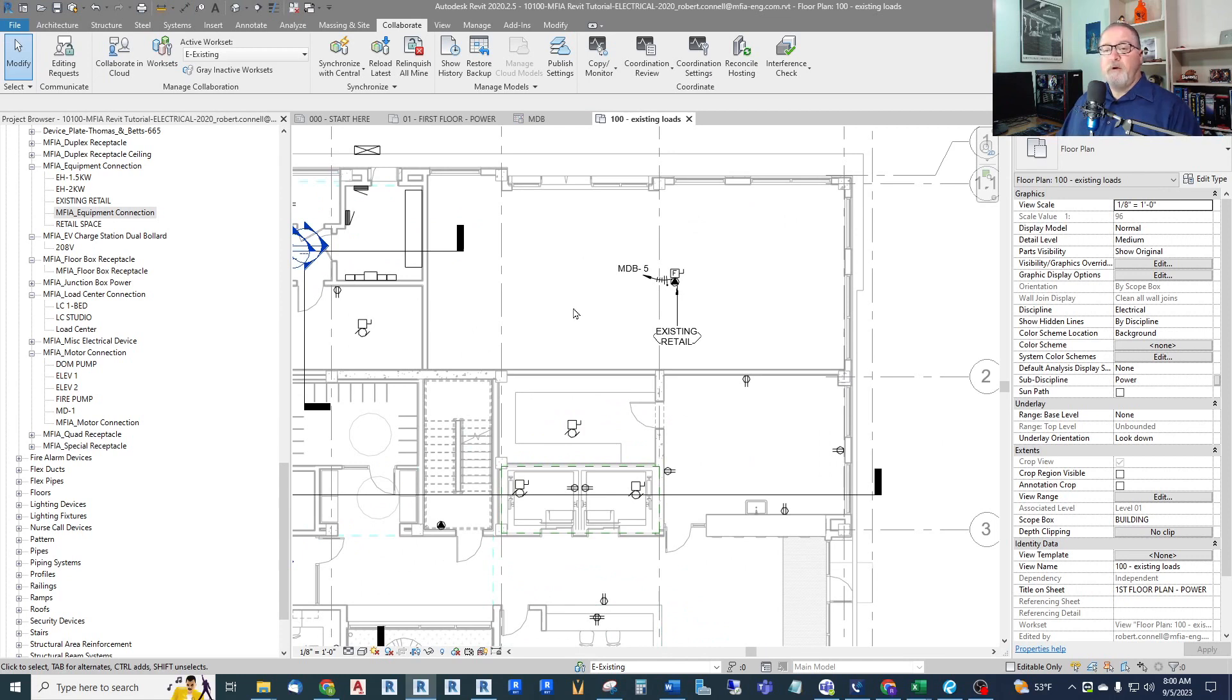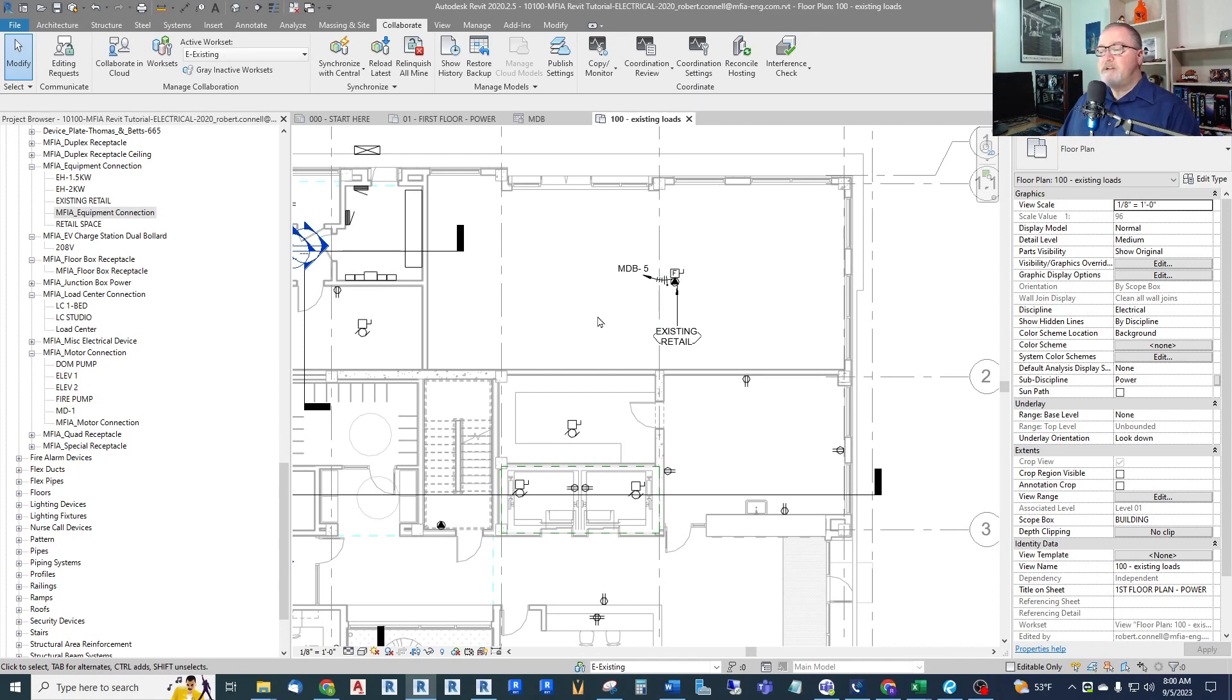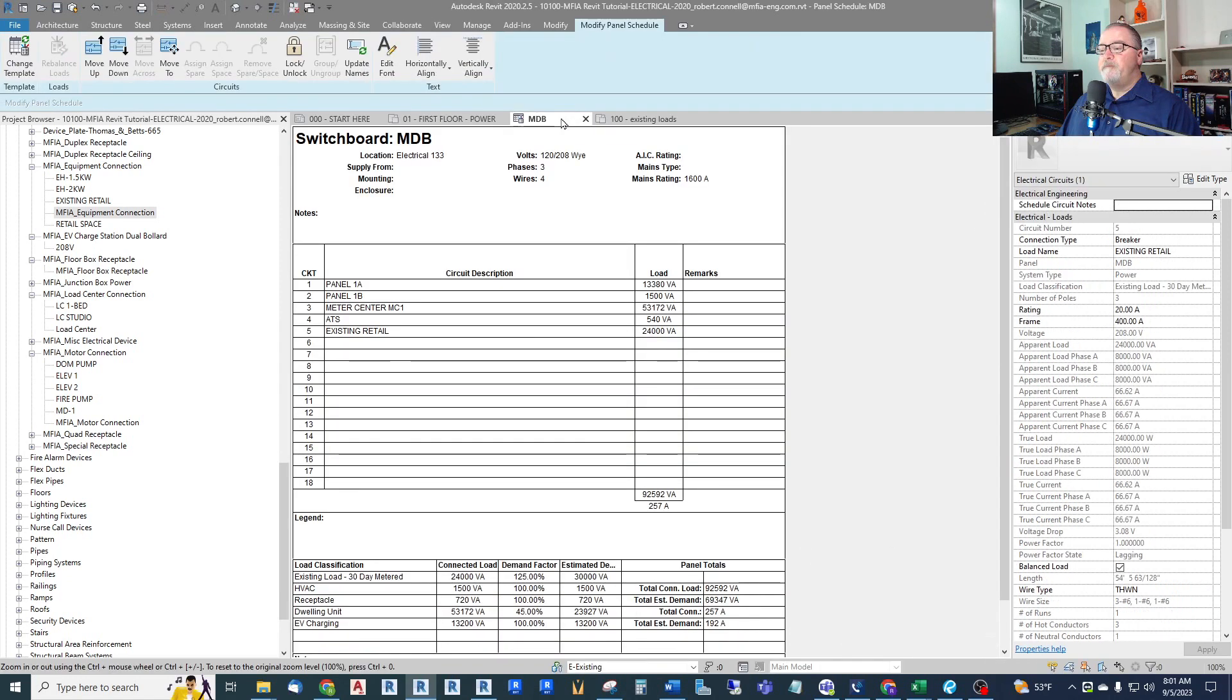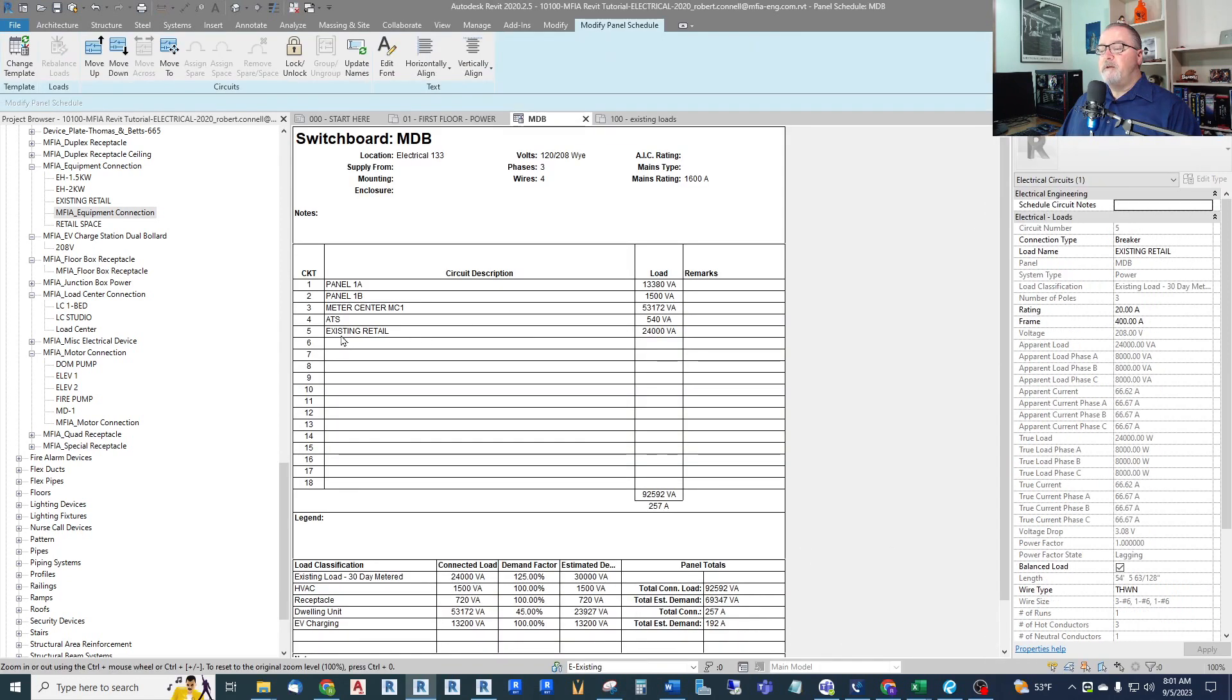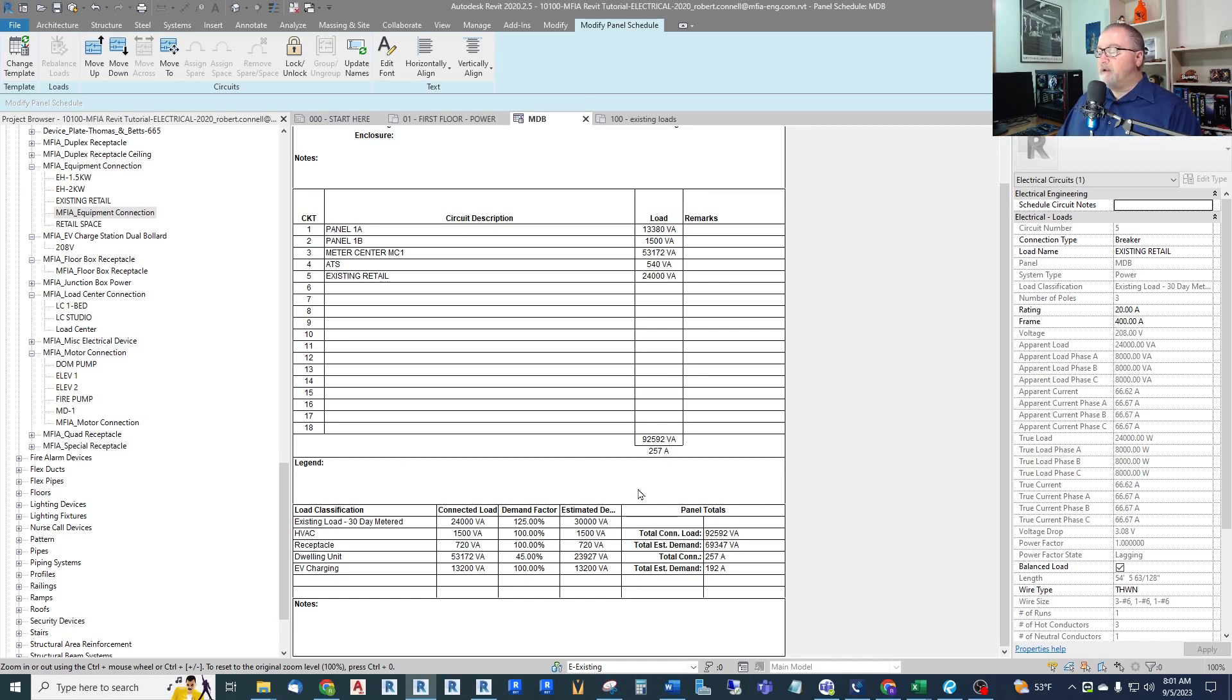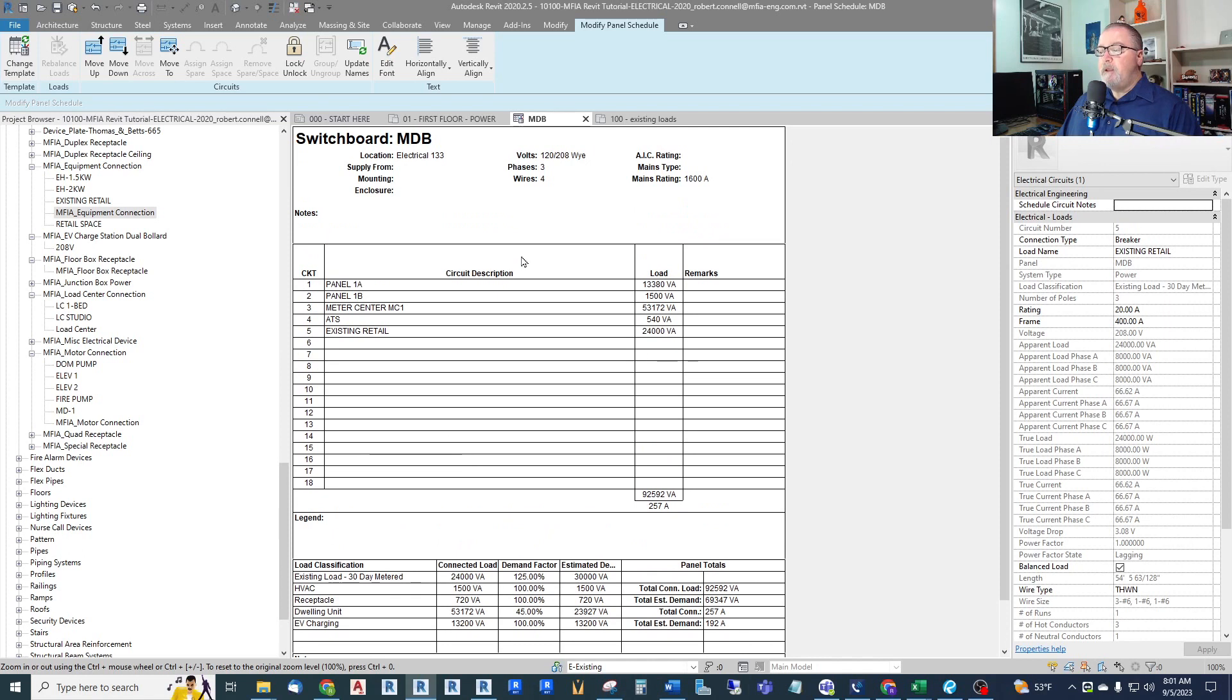So we have a record of it on this plan. I've tried it before where all of this is just hidden somewhere and then I forget where it is. So I find it best to have my own existing plan, existing view like this, where I can get to it and modify it later, add to it later. So now it's not shown on the first floor plan. Let's look at our MDB. There it is. Existing retail shows up here. It shows up down in our load classification as existing load 30 day metered. The 125% demand factor is applied and it all gets added into my load. And there we go.